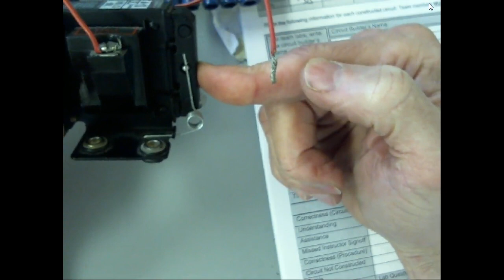And if the current drops down, because the voltage goes down, we might not have enough voltage to create enough current to keep this thing pulled in. So it might drop out. It's not, but it's not going to drop out because it still has enough voltage - we're still above the holding voltage.